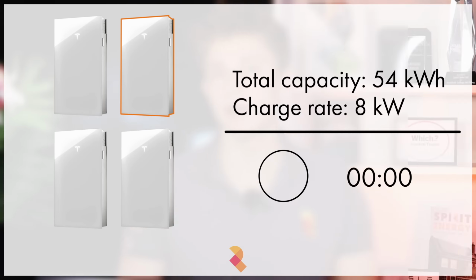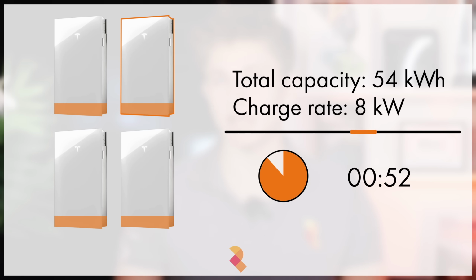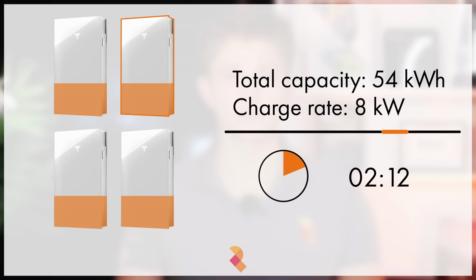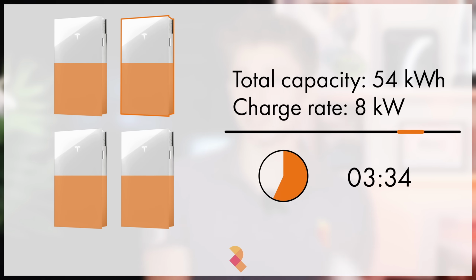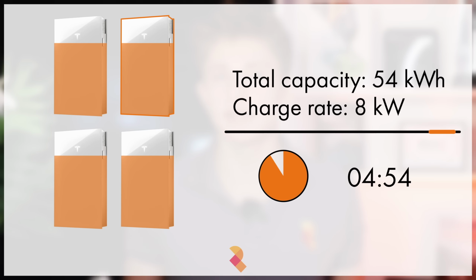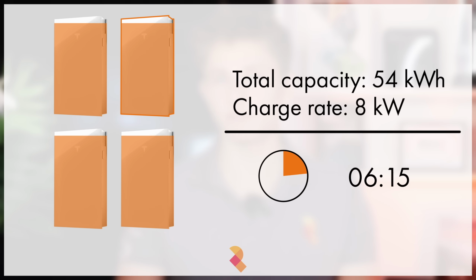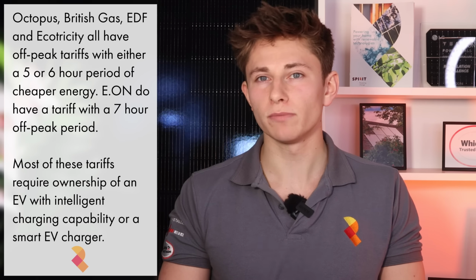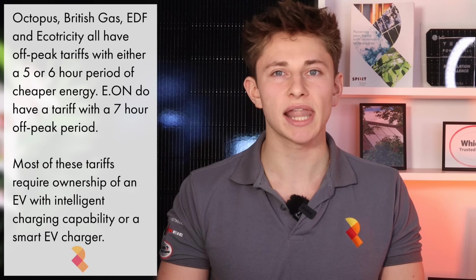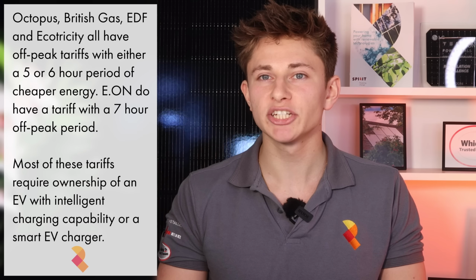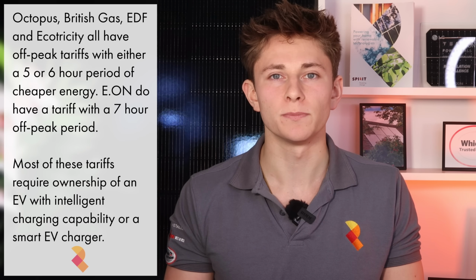This could be a consideration for those looking at larger systems. For example, a Powerwall 3 with 3 expansion packs gives you 54 kilowatt hours of total storage. Charging from 0% to 100% at 8 kilowatts would take around 6 hours and 45 minutes. That's longer than many of the current off-peak tariff windows allow, meaning that you might not be able to fully charge the system during the off-peak window. That said, this is a rare edge case, and in reality 99% of Powerwall users, even those with 3 expansion packs, will never encounter this as an issue.